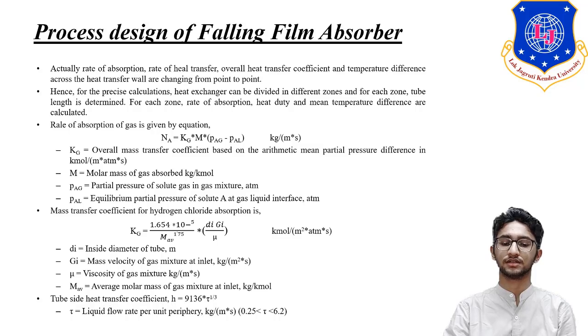Okay, then the last is the tube side heat transfer coefficient, that h equals 9136 multiplied by tau raised to 1 by 3. Now what is tau? Tau is the liquid flow rate per unit periphery, that is kg per meter second, and tau should be between the range of 0.25 to 6.2. So here the process design of the falling film absorber ends. I hope you all have understood this. Thank you.